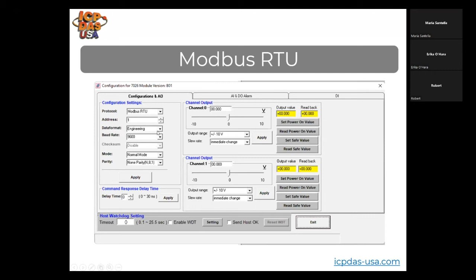Secondly, we will create a Modbus RTU connection, which is a serial-based connection using these parameters. The main ones we need to know are the Modbus RTU protocol, and the slave address of this particular module is 1. The data format is engineering, and in the next table is the register information. From the previous slide, we have COM port 4, which is what is connected to the PLC, the baud rate 9600 N81, and Modbus slave ID of 1. The registers we're going to be monitoring are 30,001 to 30,006, which are analog inputs, and 40,033 and 34, which are analog outputs.